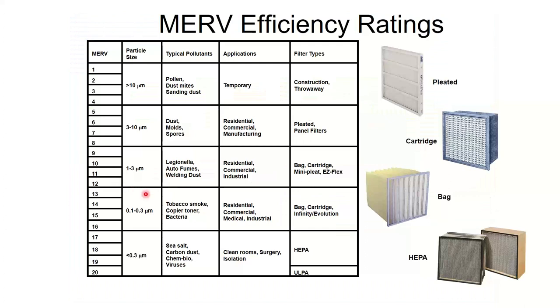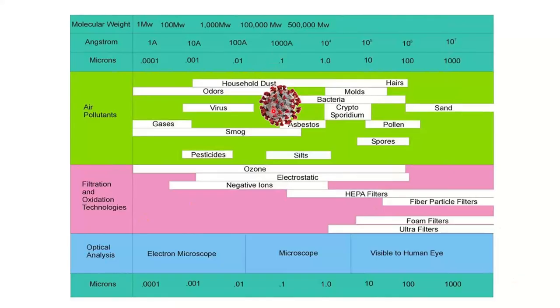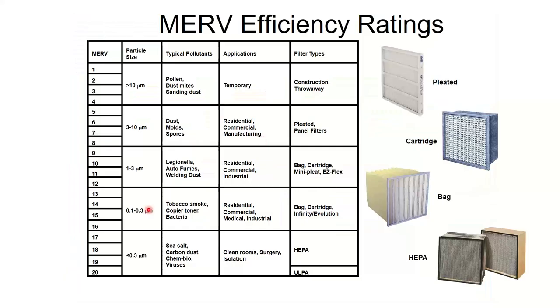If you look at the ASHRAE recommendations right now related to COVID specifically, the recommendation is MERV 14. And then it has a little caveat that says if you can't handle the pressure drop of MERV 14, we suggest maybe you try MERV 13. And we'll address that a little bit more as we move along later on, why there's that kind of gap. But for right now, let's just assume the ASHRAE recommendation is 13.5. It's somewhere between 13 and 14, if you will. That's the 0.1 to 0.3 micron size stuff. So that's the stuff right here. Really kind of on the tail end. And really to get to the 0.1 stuff, I really want to be more like MERV 15, maybe even 16.